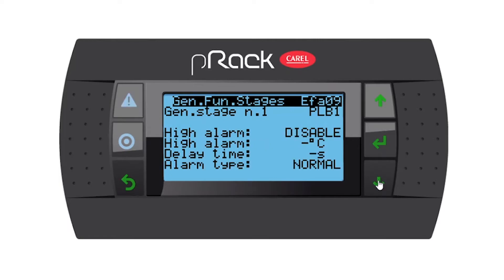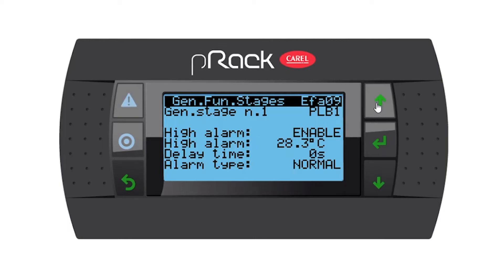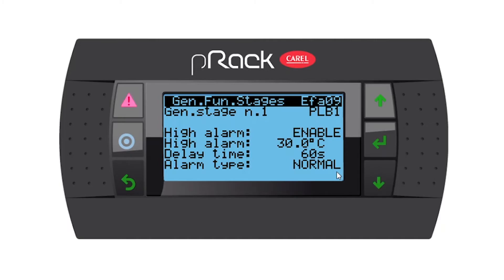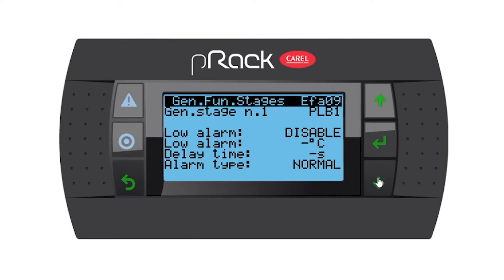Let's go down. We have high alarms — you can enable a high alarm. I'm going to set my high alarm to 30 degrees, though this is obviously dependent on you as the commissioning technician. I'll put in a delay time of maybe 60 seconds, and my alarm type is normal. You can also make it 'serious' to click your alarm relay if you've assigned one, but I'll leave it normal for now.